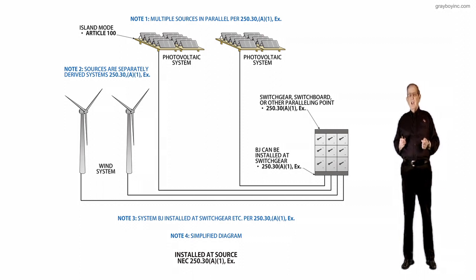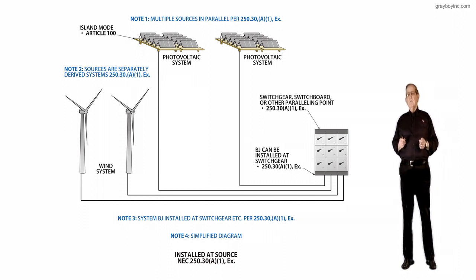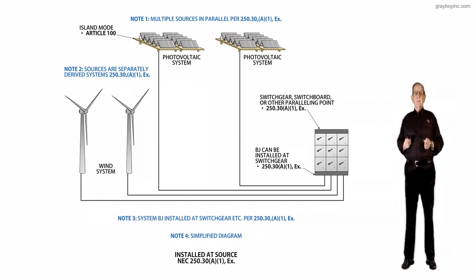The purpose of the change was to provide a new exception to address multiple sources making up a single separately derived system. The requirement would have the system bonding jumper installed at the source or the first disconnecting means. You have that option, either at the source or the first disconnecting means.